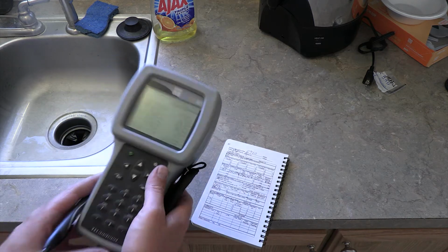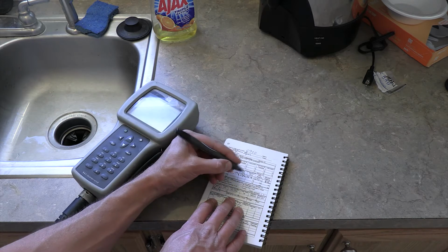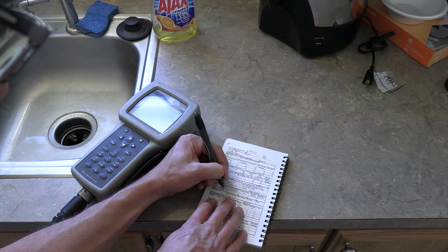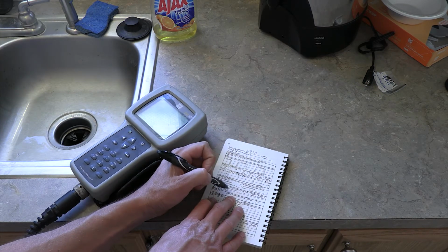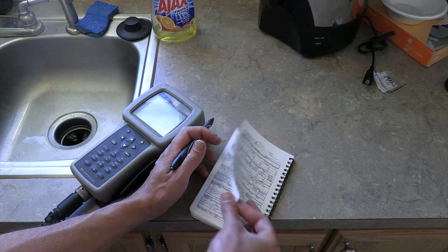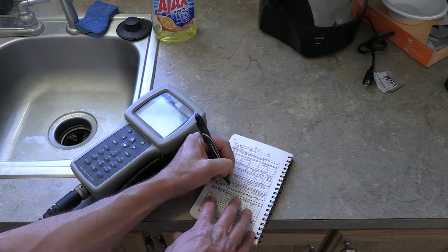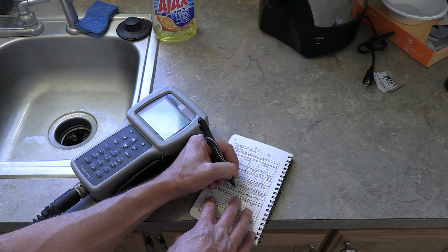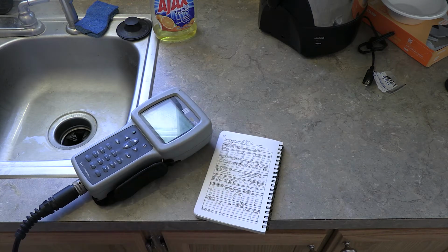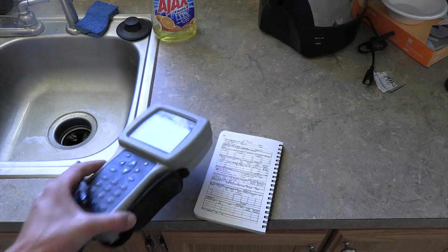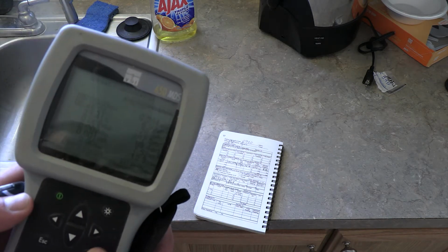We'll wait for it to start up, and then we get a temperature. So let's put our temperature in there, 23.29. And then from our saturation chart, we just looked at the last one. I think it's actually 86.6, and that's what it keeps. That's just from the chart, but you don't actually have to press that in. It automatically calibrates based on the barometric pressure.